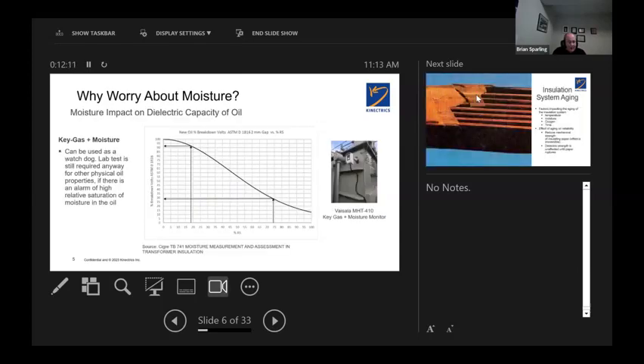The other thing is the impact on the dielectric capacity of the oil. Here we're looking at a chart from a CIGRE technical brochure, 741. It's showing, in this case for new oil, the percentage of breakdown volts to D1816, 2 millimeter gap. The left-hand side shows the breakdown volts in terms of percent, and across the bottom is the percent saturation of moisture in the oil, as measured in this case by a moisture sensor. You can see if the moisture saturation is just below 20% or at 20%, then the breakdown volts is at 90% of what it would be if it was less than 20% saturated. If that oil is like 75% saturated, that oil has lost 70% of its dielectric capacity. That's the impact of water on the dielectric capacity of the oil. It's related to moisture saturation.